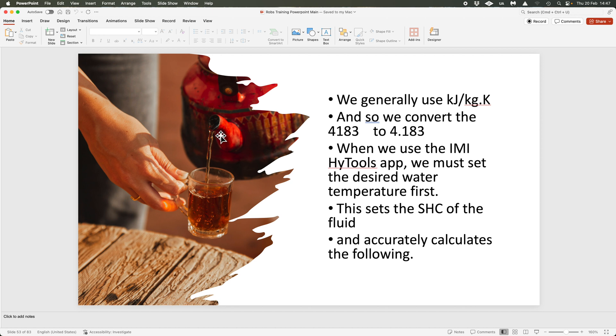A lot of tutors tend to round 4.183 up to 4.2, which is fine in domestic heating scenarios. But I have noticed on big commercial projects it can make the difference between using DN100 or DN125 pipework — if you don't get the specific heat capacity exactly right it could be right on the cusp between the two. That difference in pipe prices is horrific, so it's very important. Because we're using an app and software tools we don't need to worry too much, but for this tutorial we'll use whatever specific heat capacity corresponds to the actual flow temperature set. It will always be slightly different, and we'll play around with this with the calculator shortly.